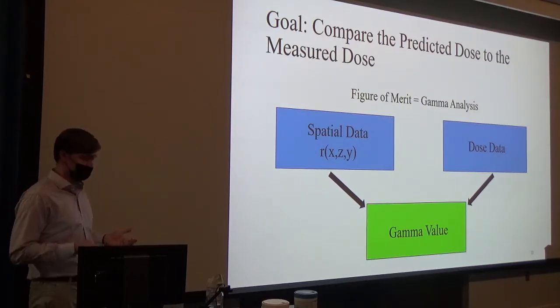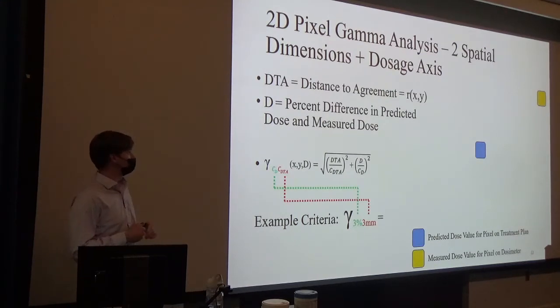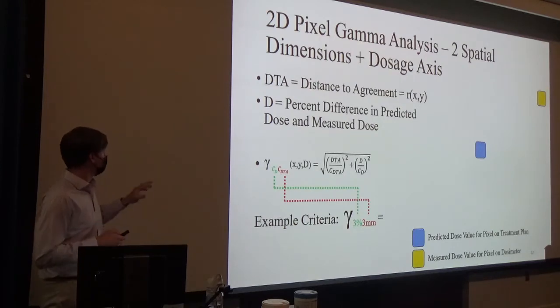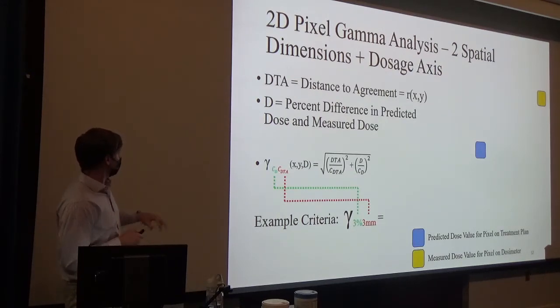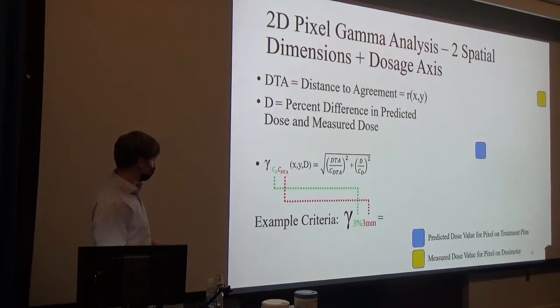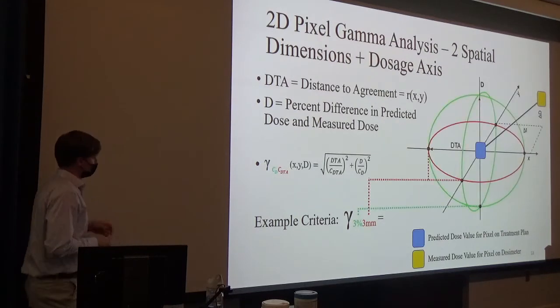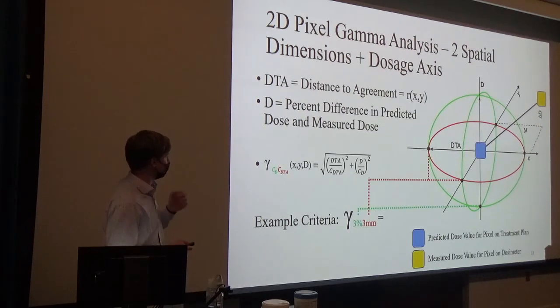We need to calculate a gamma value, which is extremely complex, so I'll explain it in two dimensions using pixels — though what we actually did was a 3D voxel gamma analysis. In 2D, you have two spatial dimensions and a dose axis. The DTA — distance to agreement — is where you are on one pixel versus the other, for predicted dose versus measured dose. Through this equation, we come up with a value and select criteria to test against. In this case, D represents the percent difference between predicted and measured dose. So this would be a 3% difference in doses within a three-millimeter search range between pixels. Applying this to a graph, the red circle is the spatial component — a 3mm range on the X and Y axes — and the dose comparison, the percent difference, is on the Z axis. This forms a volume, or ellipsoid.